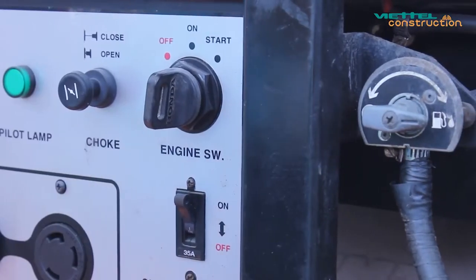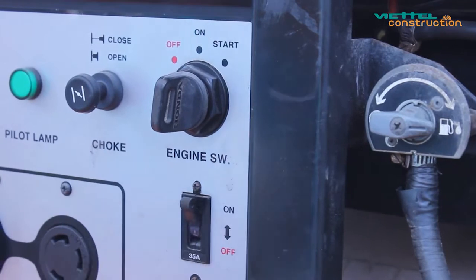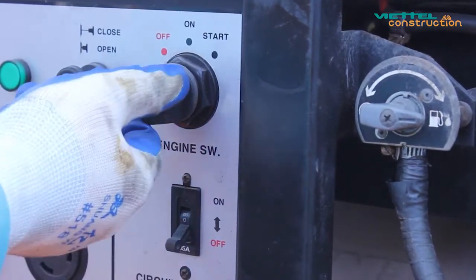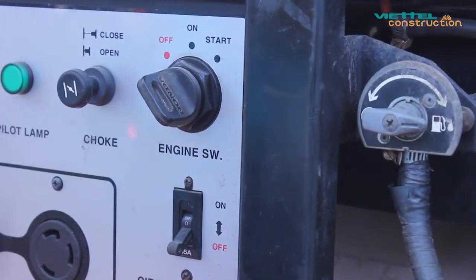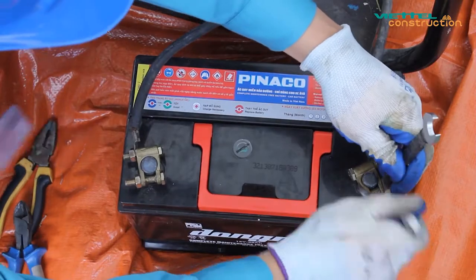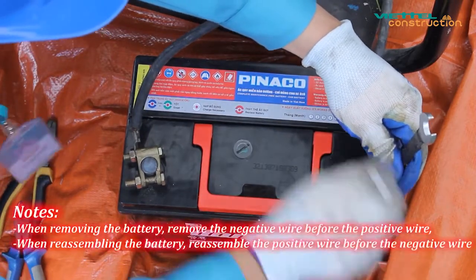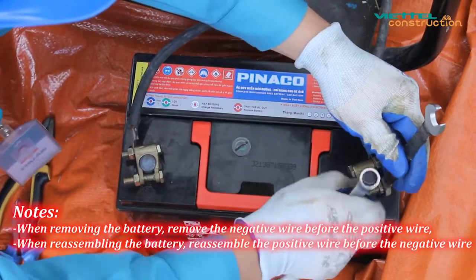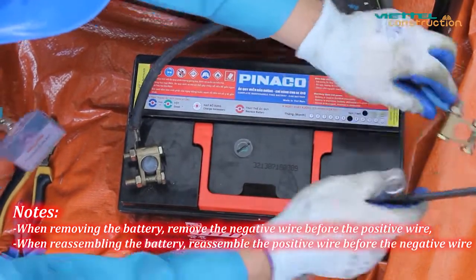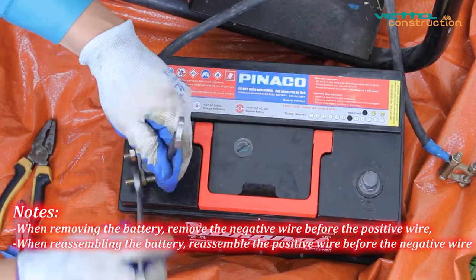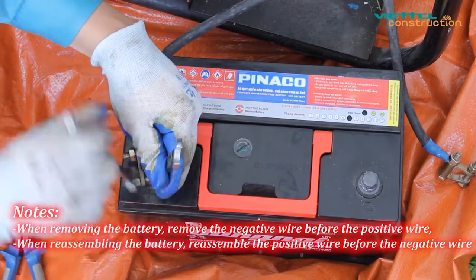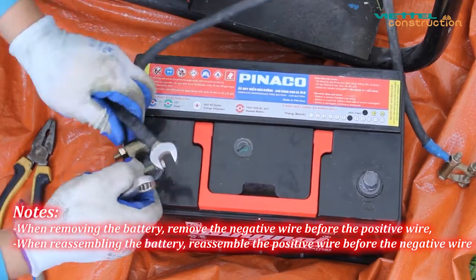Step 2. Maintenance and cleaning of the electricity system. Before checking, we proceed to turn off the generator, disconnect the power, remove the battery to ensure electrical safety during maintenance. Notes: when removing the battery, remove the negative wire before the positive wire. When reassembling the battery, reassemble the positive wire before the negative wire.